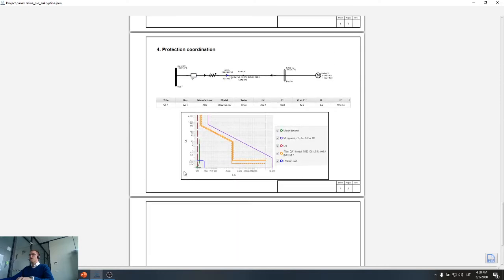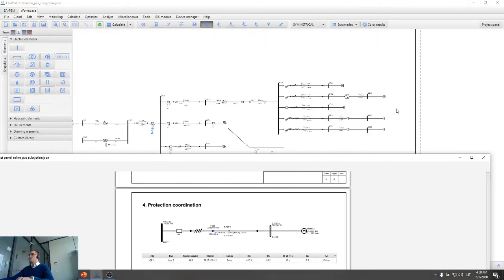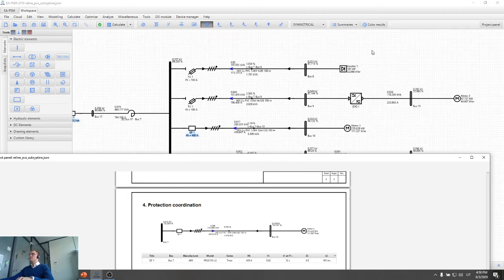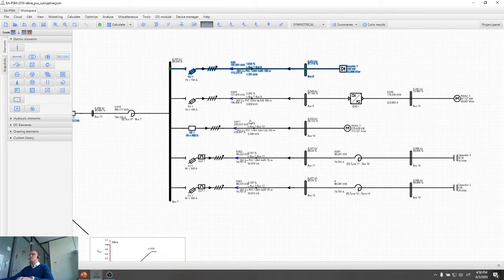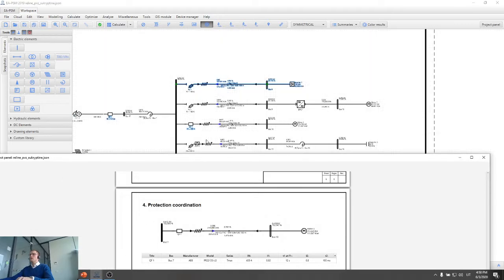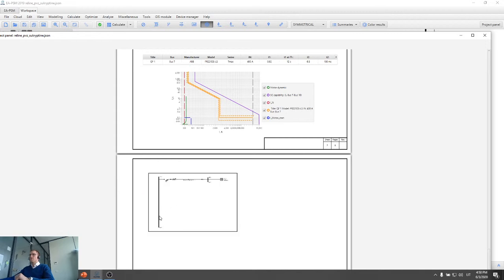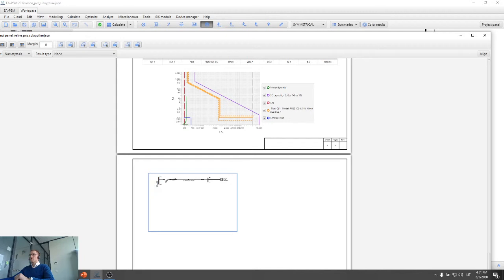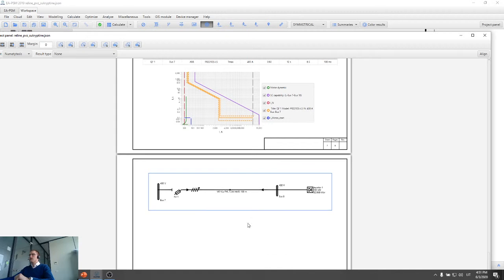So let's add maybe one more example. So I will add one more page. Let's go to the network here. For example, I will highlight the inverter with the fuse and the cable. Yes. So I will add the scheme view for the inverter. So the bus bar will be normal size, but you can always reduce it and increase the single line diagram size. Now I can add information about the power flow results in order to provide for the customer. Now I can also add the fuse itself.